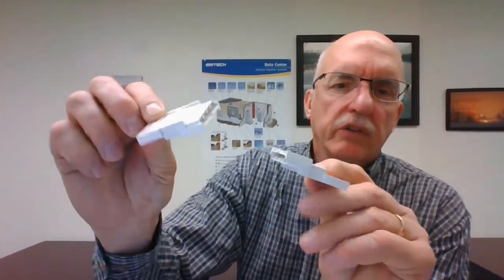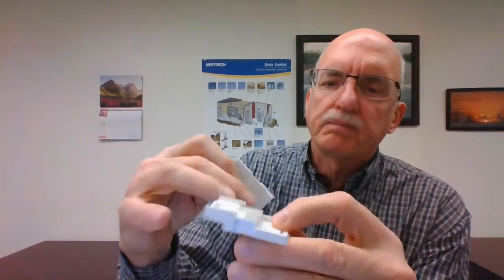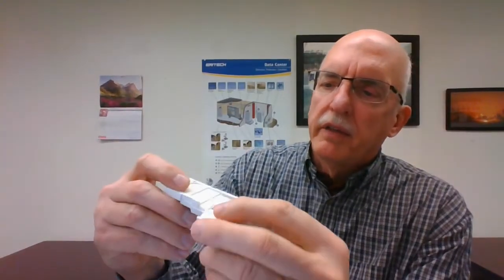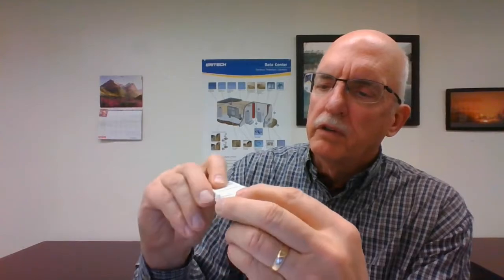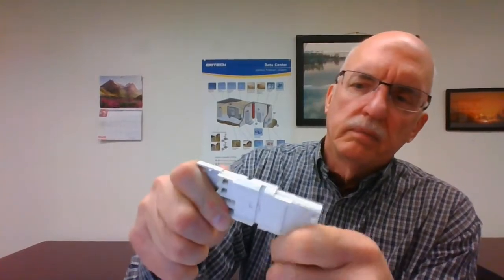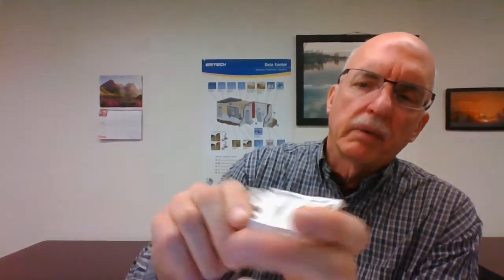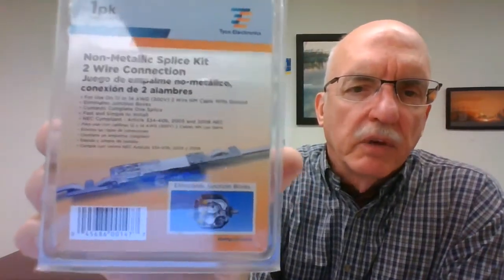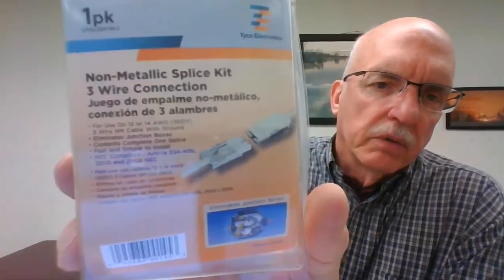It's a Tyco connector, two pieces. You put the Romex terminated in here on these steps, terminate on this side here, and then you're going to slide the two halves together. And then snap them in together. They're not going to come apart. All right. So Tyco makes these. Take a picture of that if you want. This is a 2-wire connector, and then they also have 3-wire connectors for your 3-way systems, 3-way lighting, things like that. So they're a little bit pricey.